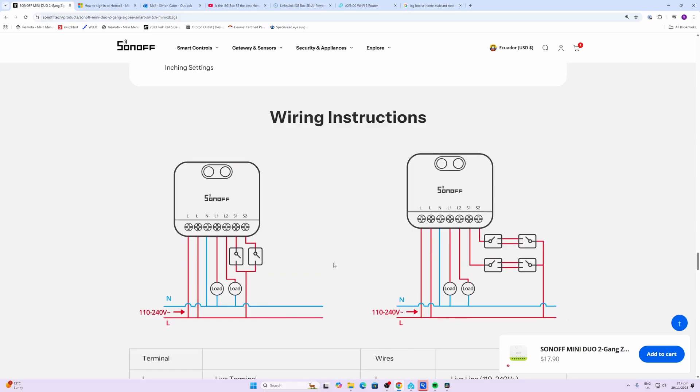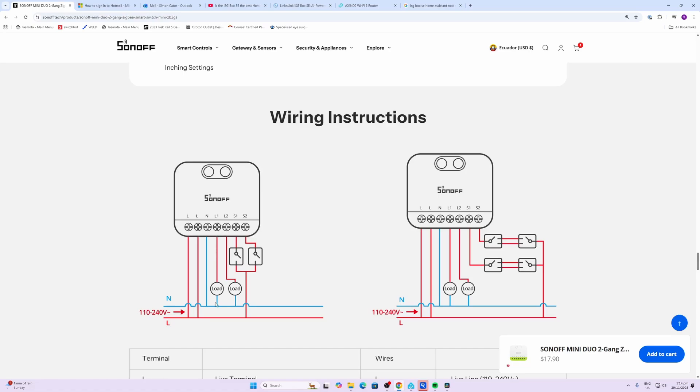Wiring these devices is really simple, but always get an electrician involved unless you're qualified to do so. Basically you bring your live and your neutral wires in, and then your loads are supported from L1 and L2 back to neutral, and your two switches go from S1 and S2 back to the live wire.